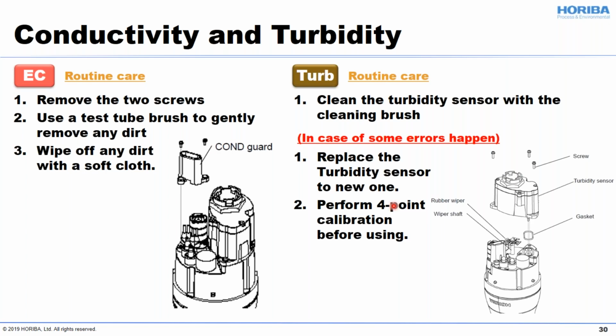For turbidity, you can use a brush to clean inside, similar to the electric conductivity sensor, but this isn't needed often. If you find errors with the turbidity sensor, it will be indicated on the meter. We have a spare turbidity unit available as a replacement part, so you can change it yourself. If you replace it, the important point is that you need to conduct calibration again — but no need to return it to us, you can replace it yourself.